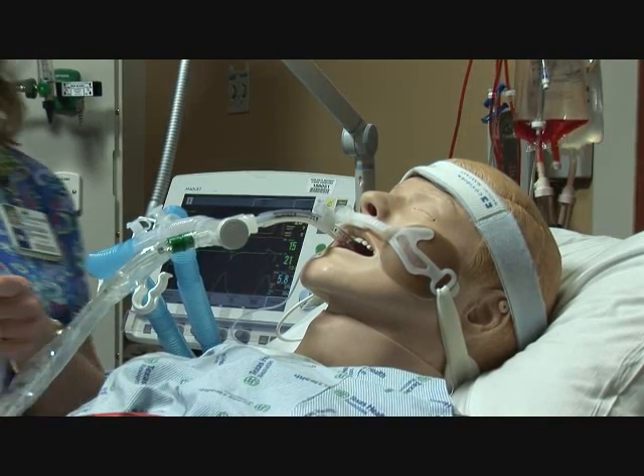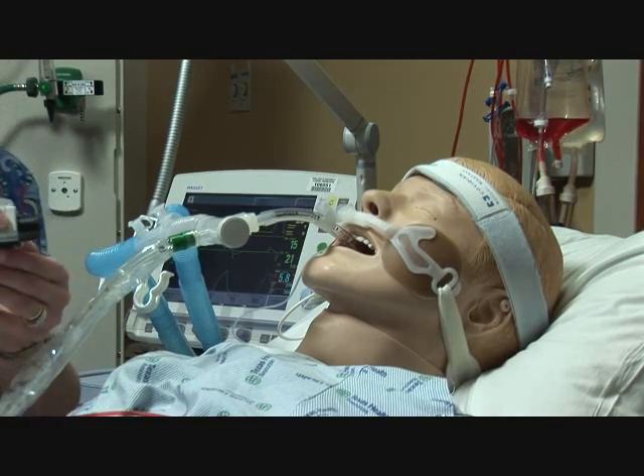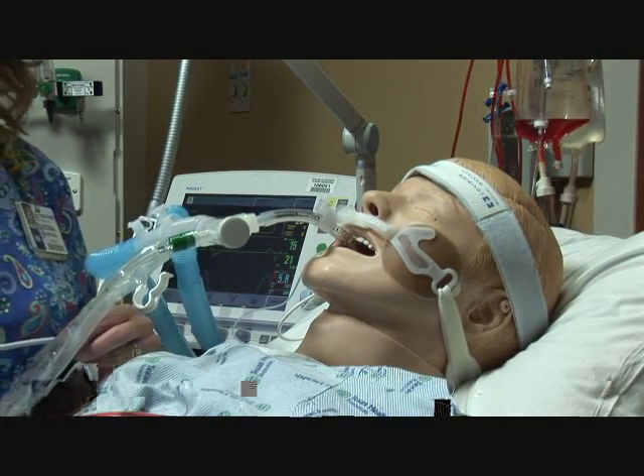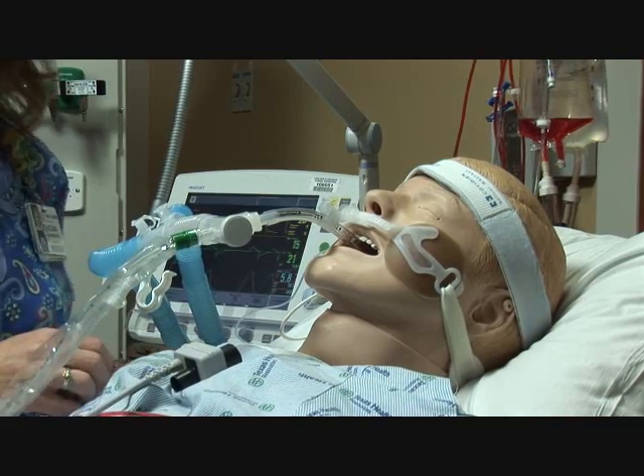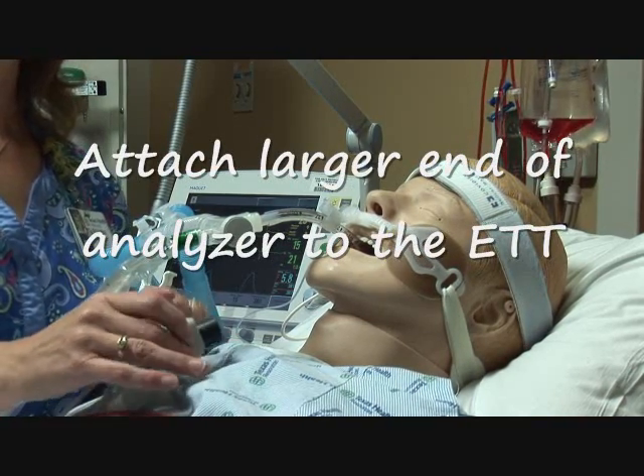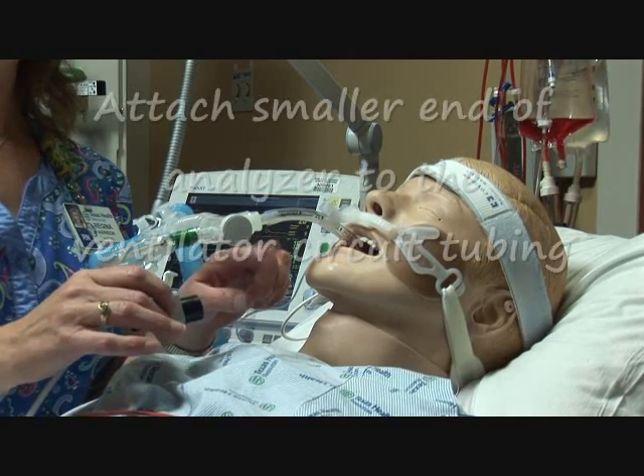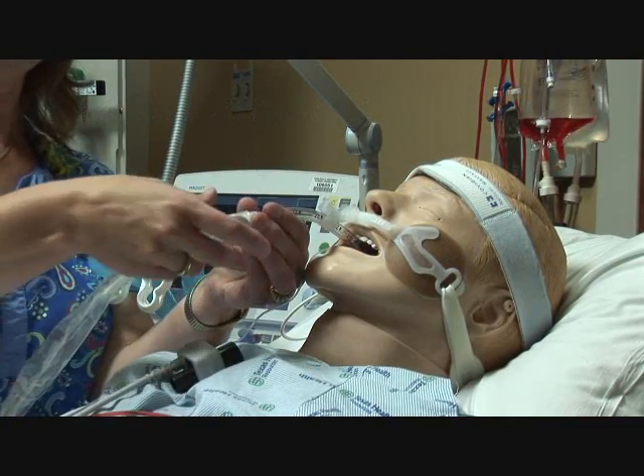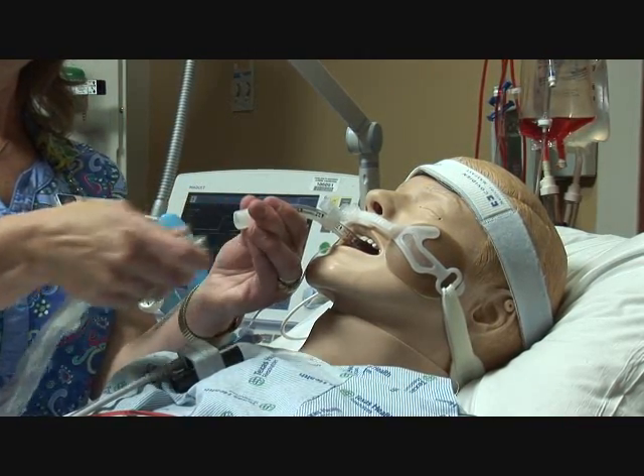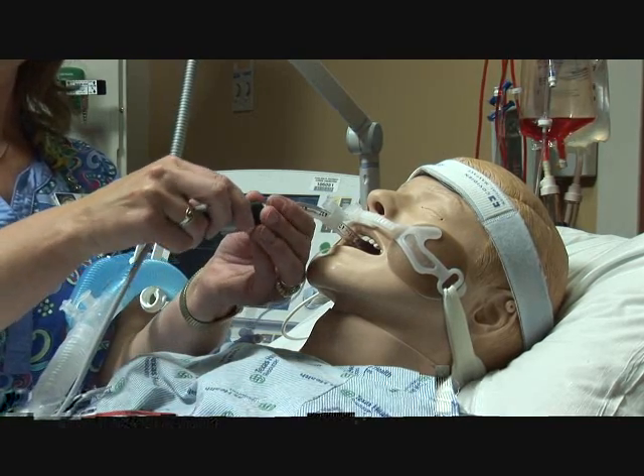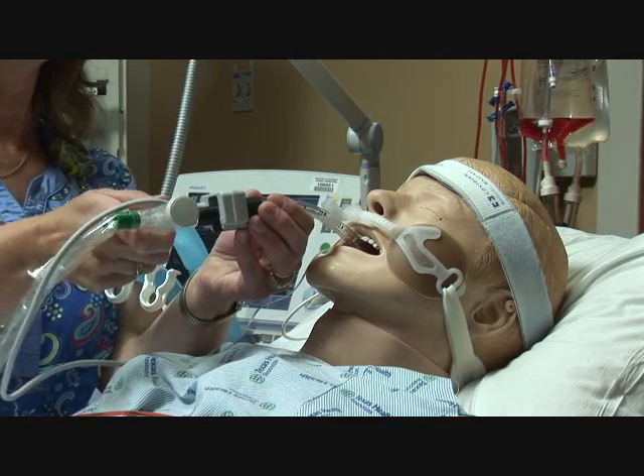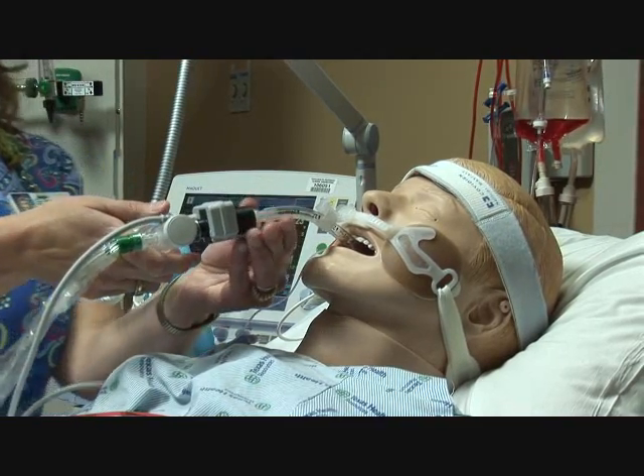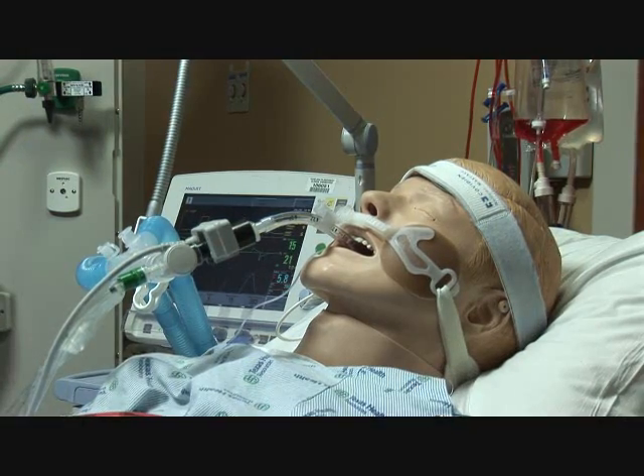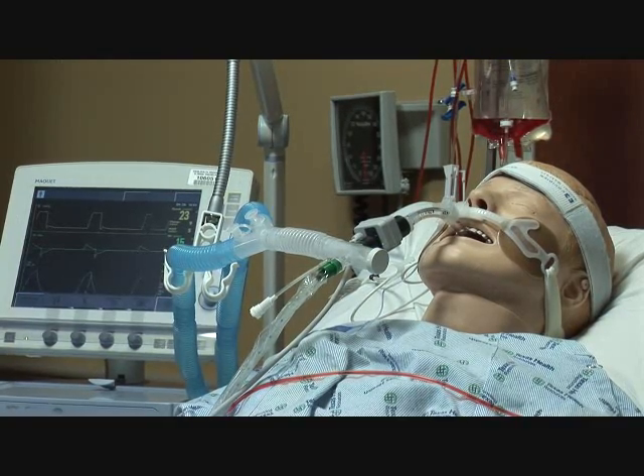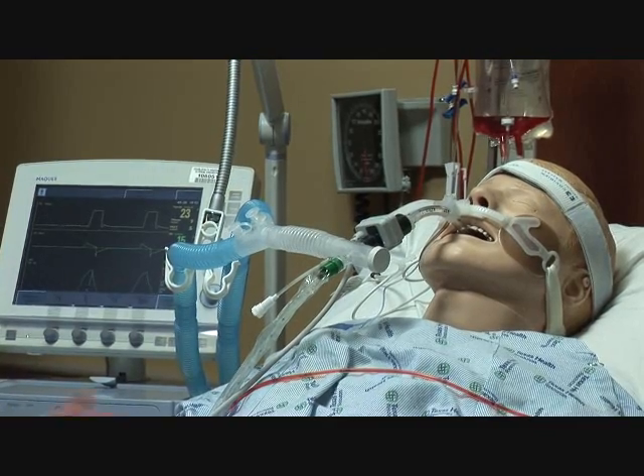And now we're going to attach the analyzer to the ET tube and ventilator, and you want to make sure that you have it all ready to go so we don't lose any ventilation. You would attach the larger tube to the ET tube and the smaller tube to the circuit. So you want to hold on to the ET tube for security and detach, and then hook the larger tube up and then the smaller tube to the circuit. And then you're ready to analyze. Travis, do you have any questions about how to hook that up? No.